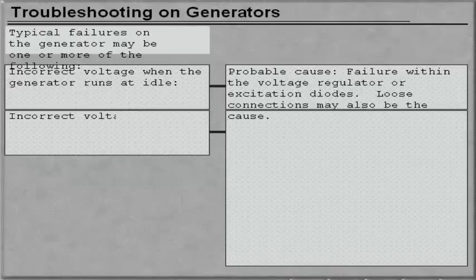Some circuit breakers may have pneumatic delay relays, which tend to change delay time due to dirt. These have to be cleaned and checked, eventually readjusted. Inspection of the instrument's accuracy may be carried out according to maintenance schedule. Inspect the generator circuit breakers in accordance with manufacturer's recommendations.